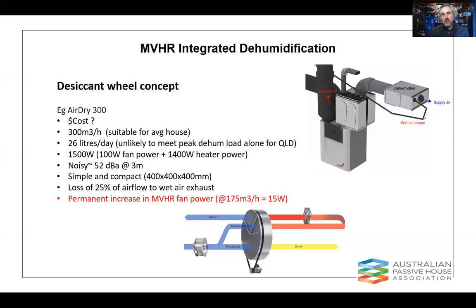And if we look in the top right corner, I've sketched in the wet air stream. It's not a condensate drain, so the moisture is still in gaseous form. The water's still suspended, and so we can discharge that. We could link that back into the HRV exhaust and discharge it that way. The other thing to note for this and the next solution is that both of them have permanent fan power increases. And when I say that, I mean in the MVHR fan power.